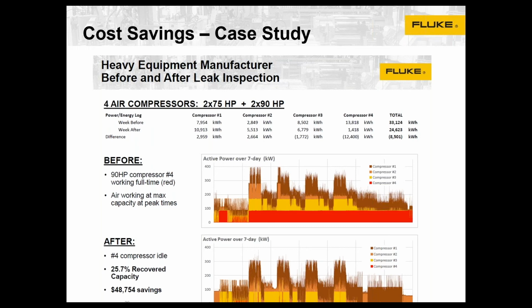Just to make it a little bit more real, here's an actual cost savings with a customer that was a novice really with the acoustic imagers, and they had 4 compressors on site, and what they did was they actually used a Fluke power logger to monitor the energy consumption from their compressors. So they did a before study, performed leak inspection, repaired leaks, and then did an after. So you can kind of see what that looks like before, modeled a little more visually.